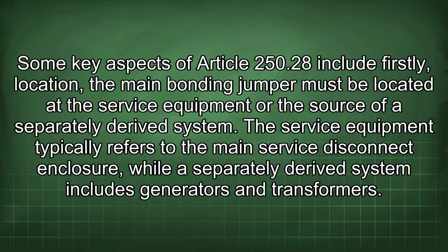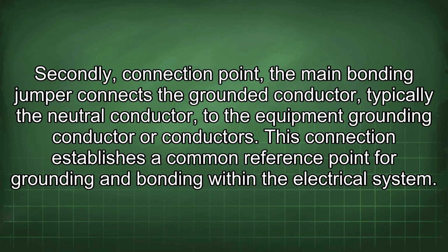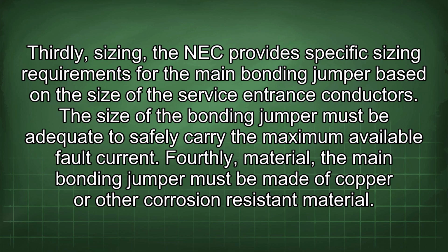Some key aspects of Article 250.28 include: firstly, location. The main bonding jumper must be located at the service equipment or the source of a separately derived system. The service equipment typically refers to the main service disconnect enclosure, while a separately derived system includes generators and transformers. Secondly, connection point. The main bonding jumper connects the grounded conductor, typically the neutral conductor, to the equipment grounding conductor or conductors. This connection establishes a common reference point for grounding and bonding within the electrical system. Thirdly, sizing. The NEC provides specific sizing requirements for the main bonding jumper based on the size of the service entrance conductors. The size of the bonding jumper must be adequate to safely carry the maximum available fault current.